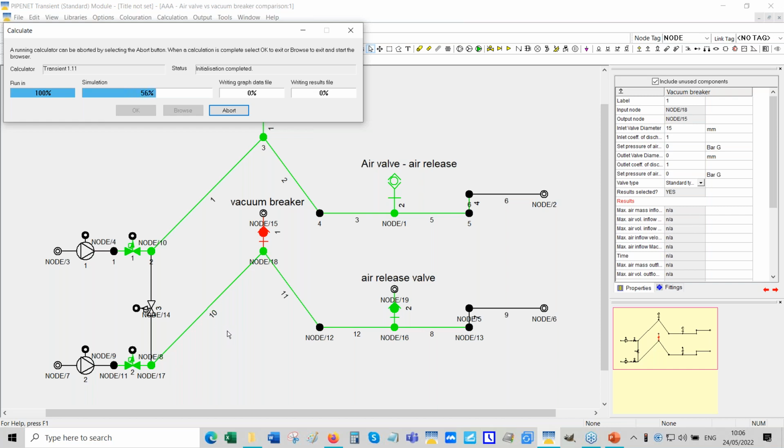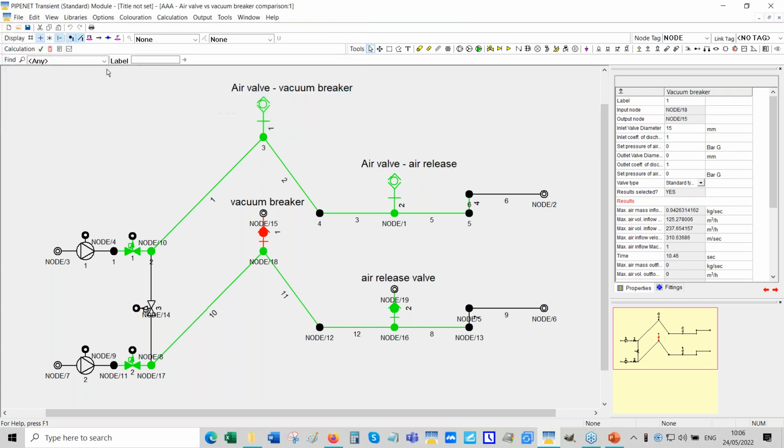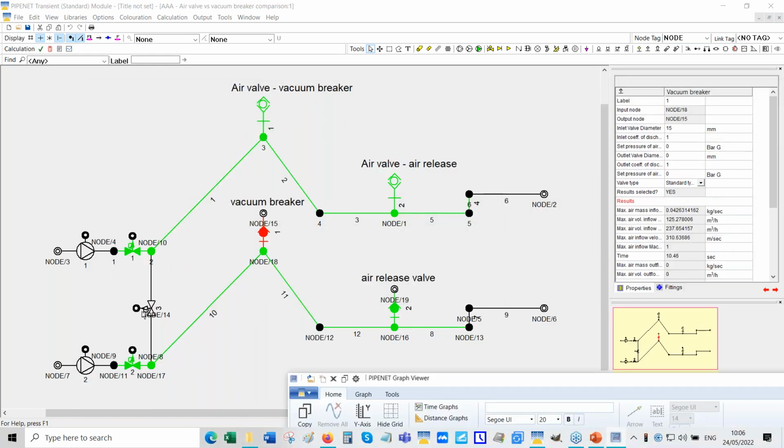See, these simulations are actually very complex, because you can see how difficult it is to model how the air pocket moves through the system. Comes in here, moves down this line, and goes out through there. That is reality, but you can imagine how difficult it is to model that. This is pipe 10, pipe 1. Pipe 1 is, by the way, this valve is closed. You know, we've got this valve and it's closed only to make sure we have one connected network. That's what we need.